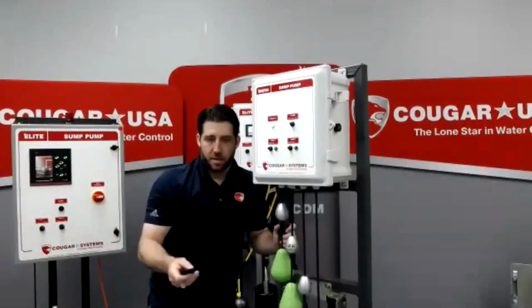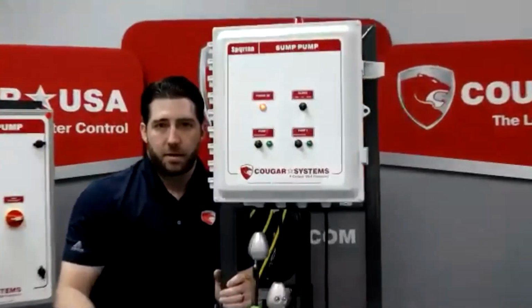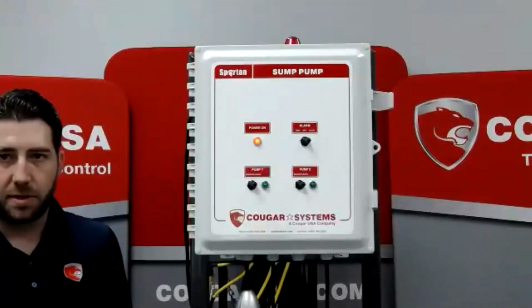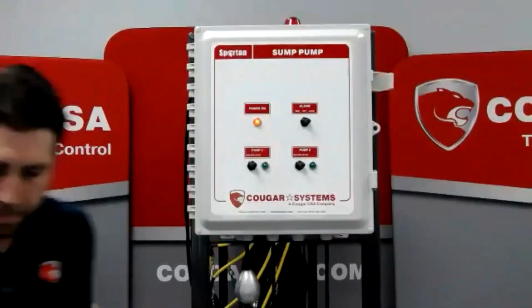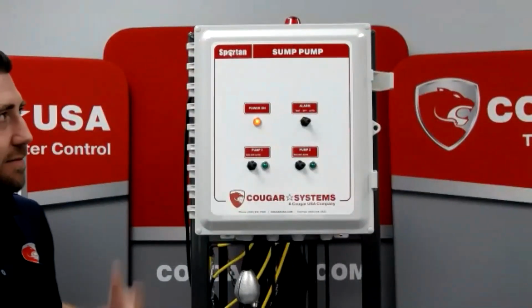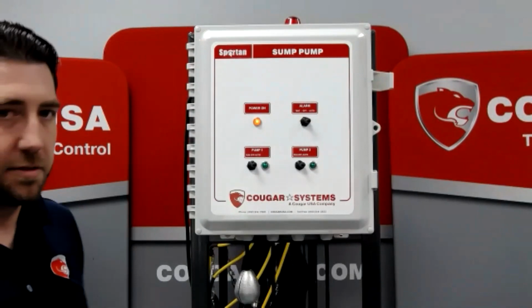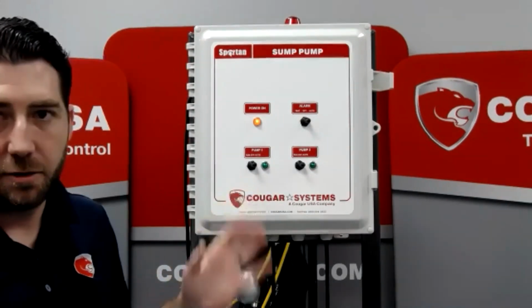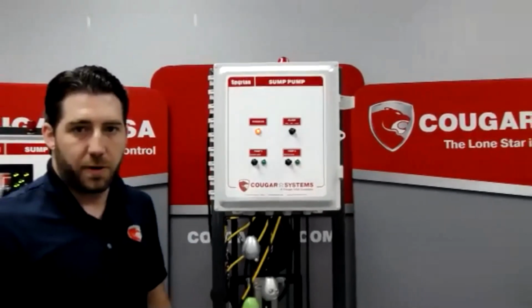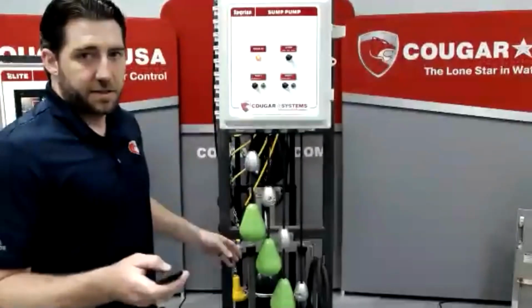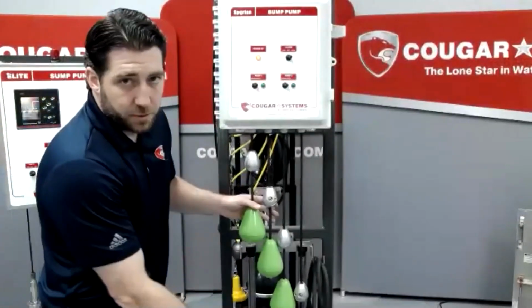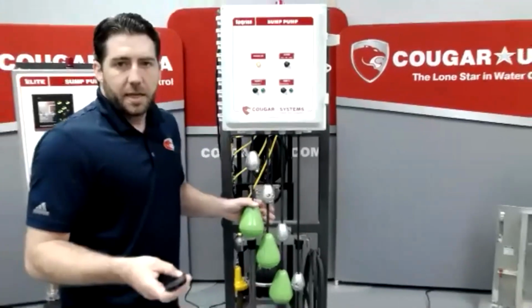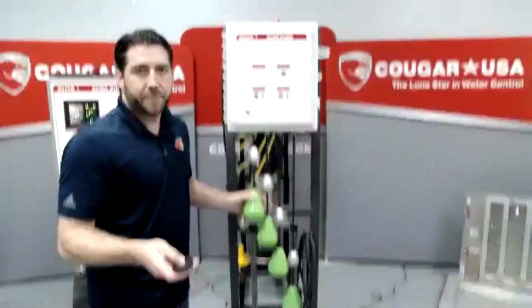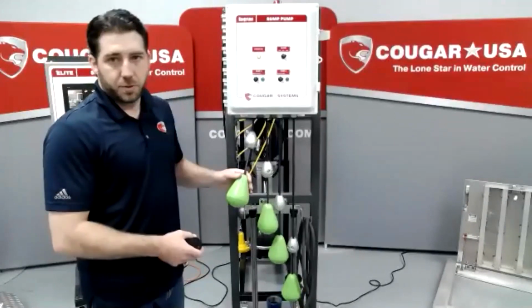So the control panel here that we have paired with this one, we call this our Spartan series, but basically this is a relay logic style control panel, and this one is set up for 4-float operation. And again, you can see these float switches here in the 4-float switch configuration. And really, these are going to be the standard float switches that we use.